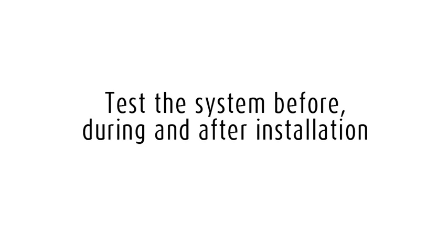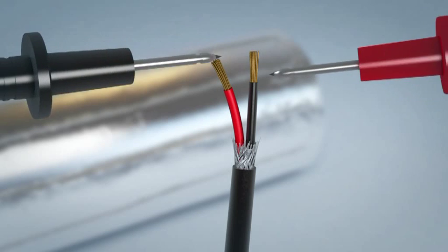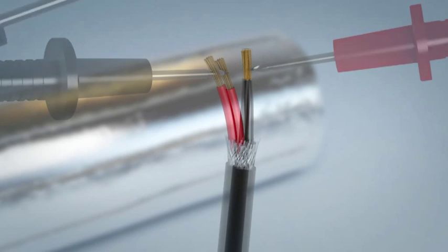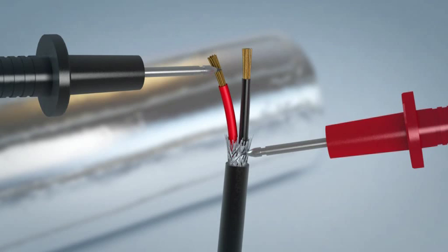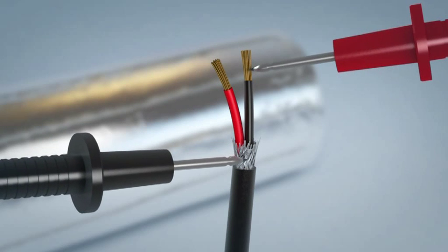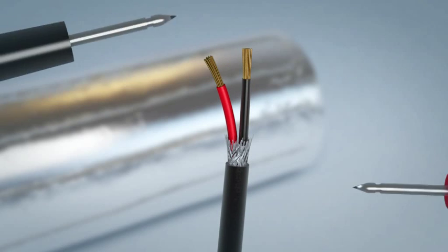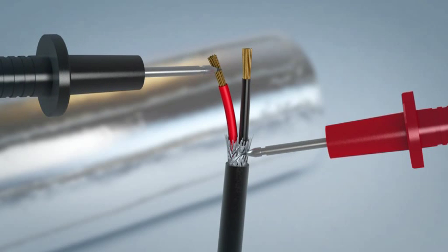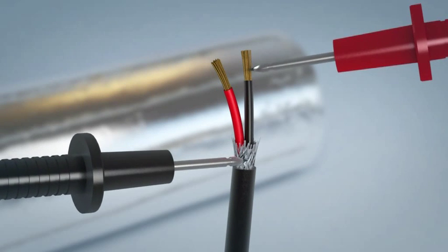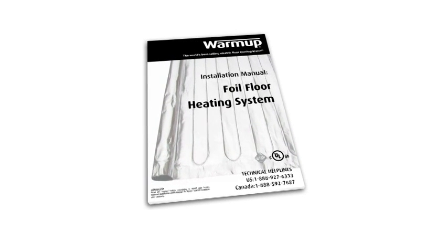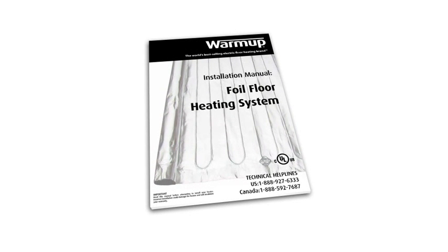It is important to test the system before, during, and after the installation. Check that the resistance between the two conductors matches the resistance shown in the manual and at the end of the cold lead label on each mat. Also check that the reading between each conductor and ground is completely open and that there is no resistance reading. Record your readings in the Warm-up installation manual for warranty registration.